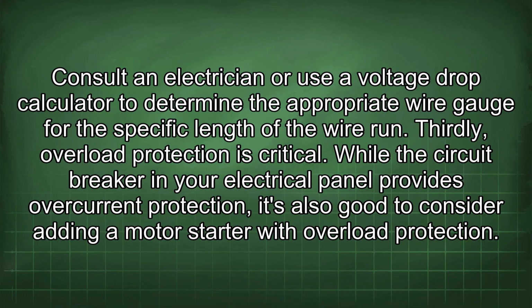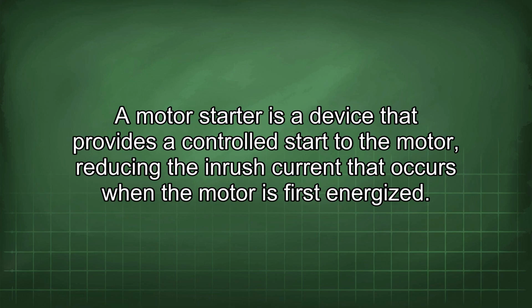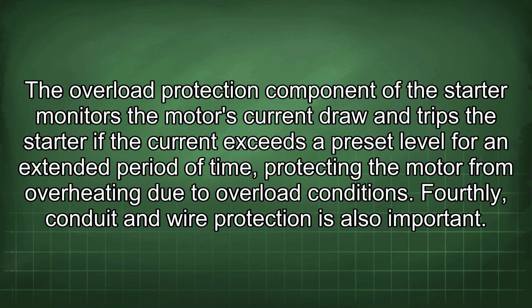While the circuit breaker in your electrical panel provides overcurrent protection, it's also good to consider adding a motor starter with overload protection. A motor starter is a device that provides a controlled start to the motor, reducing the inrush current that occurs when the motor is first energized. The overload protection component of the starter monitors the motor's current draw and trips the starter if the current exceeds a preset level for an extended period of time, protecting the motor from overheating due to overload conditions.